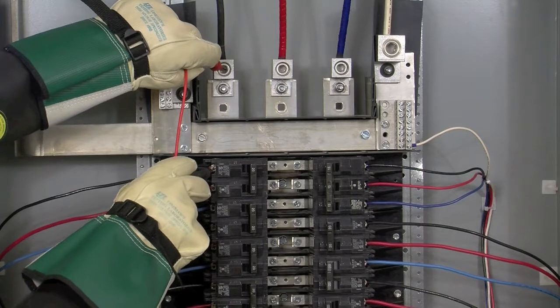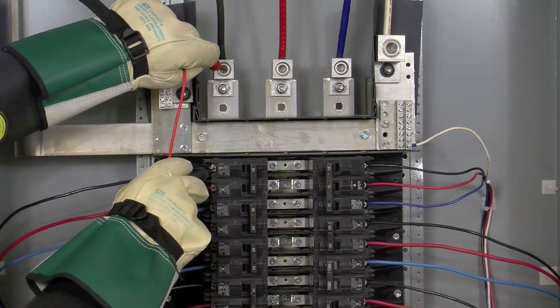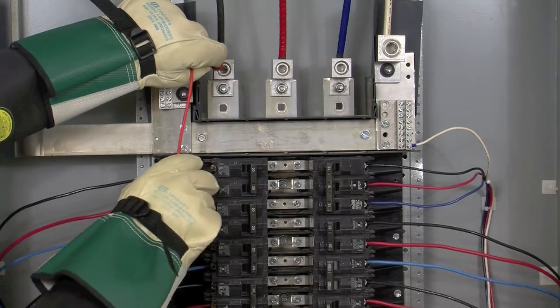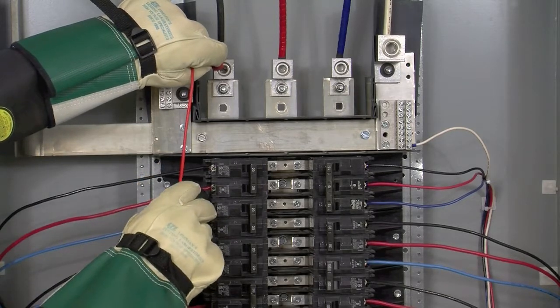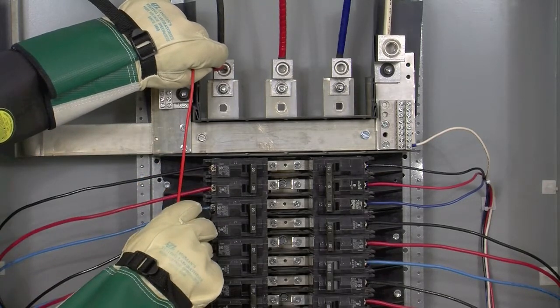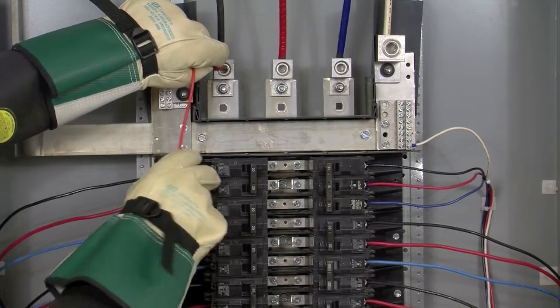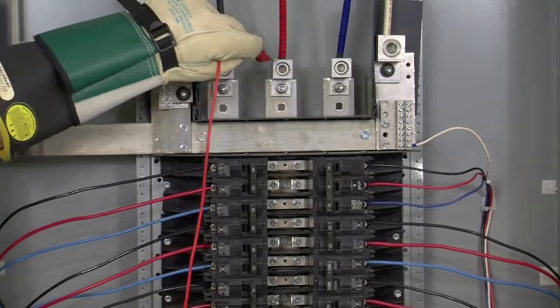If it was any other phase, we would have a voltage difference, and in a panel like this, it would be roughly 208 volts. So here we have 0 volts difference. Here we have 208, and here we have 208. Once again, here we have 0, so we know that the top pole here is phase A. Moving on to phase B.